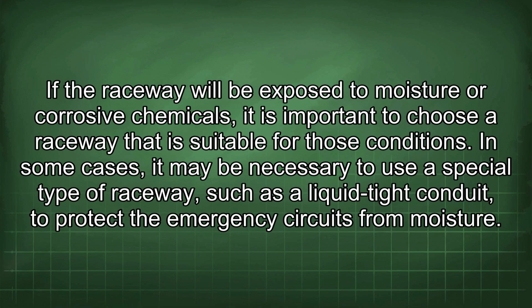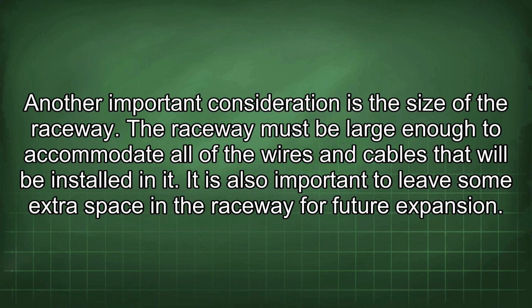In some cases, it may be necessary to use a special type of raceway, such as a liquid-tight conduit, to protect the emergency circuits from moisture. Another important consideration is the size of the raceway. The raceway must be large enough to accommodate all of the wires and cables that will be installed in it. It is also important to leave some extra space in the raceway for future expansion.